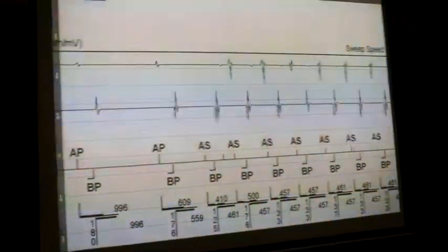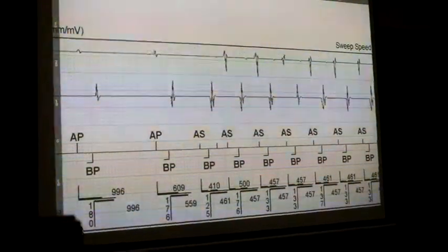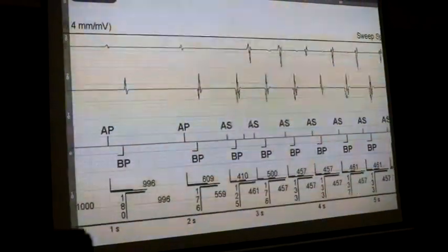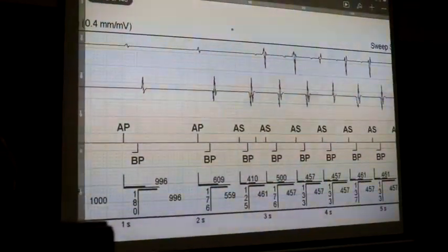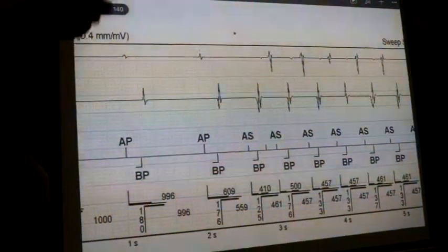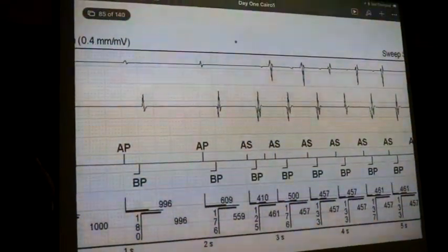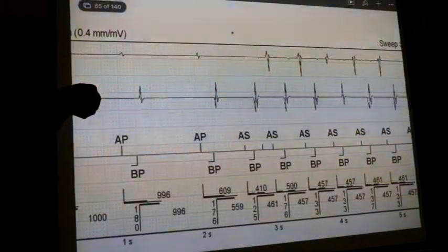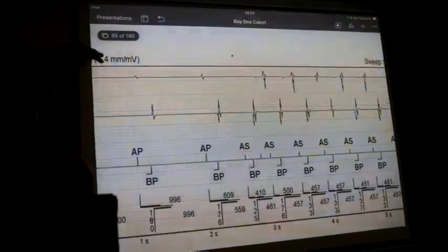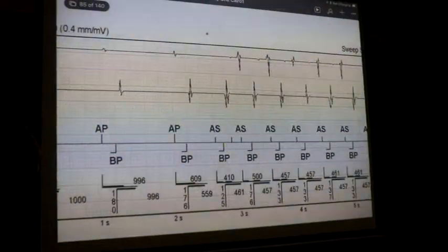So sometimes people get annoyed and they say, right, it senses stuff and I can't see anything. And then they call the device stupid and say bad things to me and upset me sometimes. We've got noise, right? There's noise on that atrial lead. The resolution on this is lower than the resolution that the device is sensing at, okay? So you will, on reasonably rare occasions, see nothing on here, but the device has seen something, okay? We can't run the same resolution on a piece of paper that the device can work out, okay? So there is a different resolution.